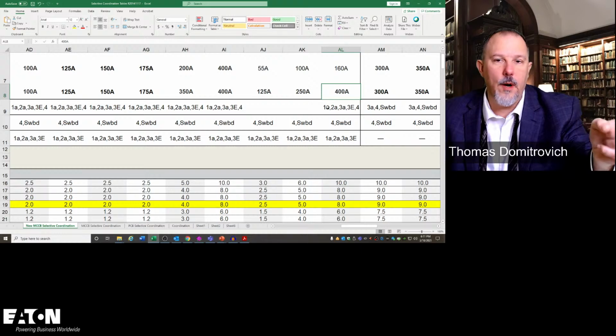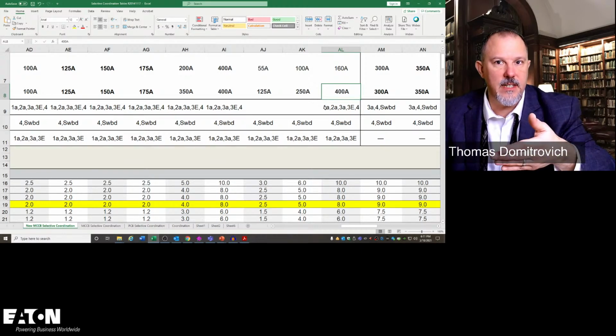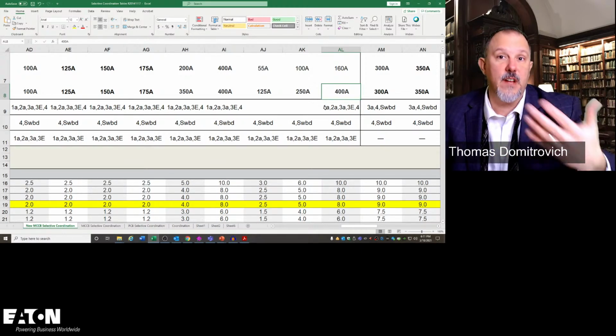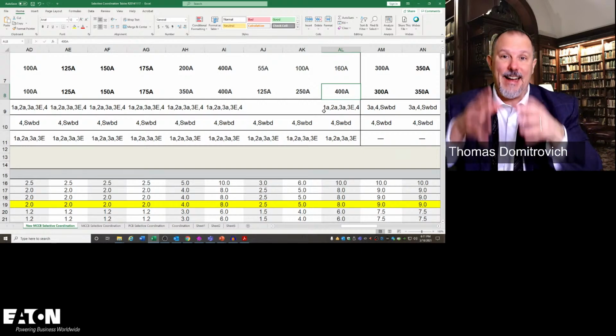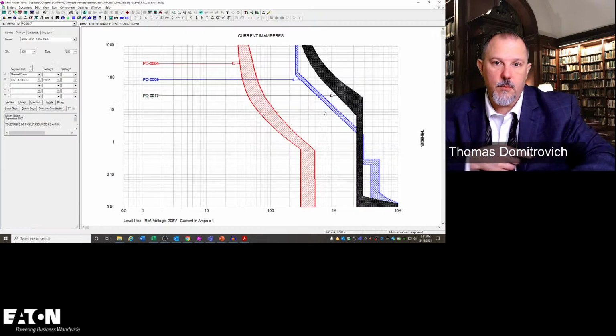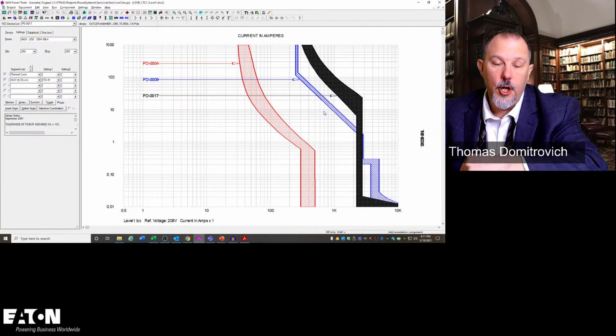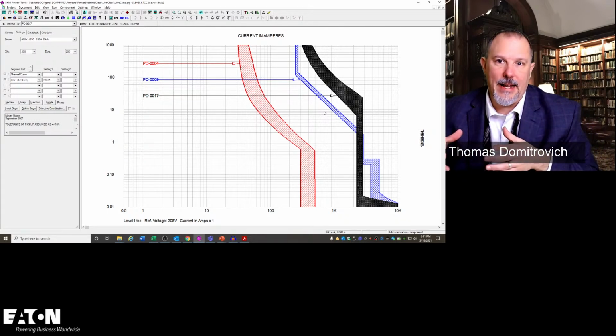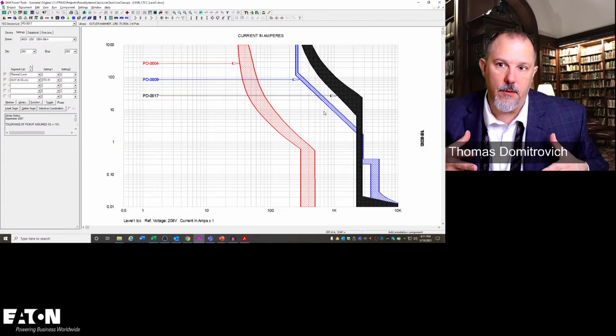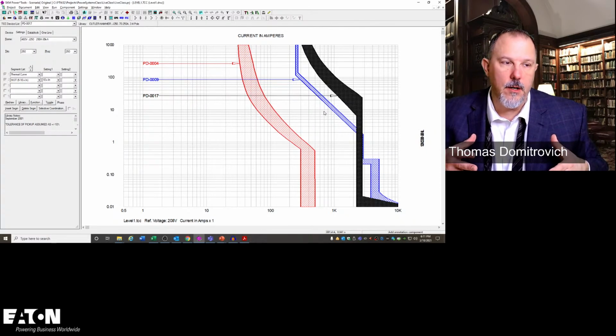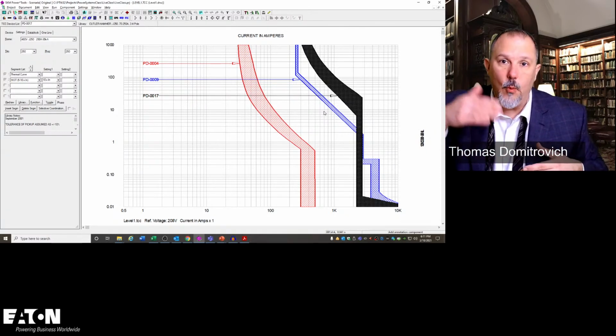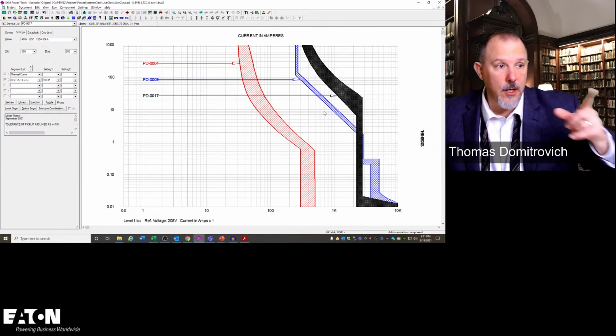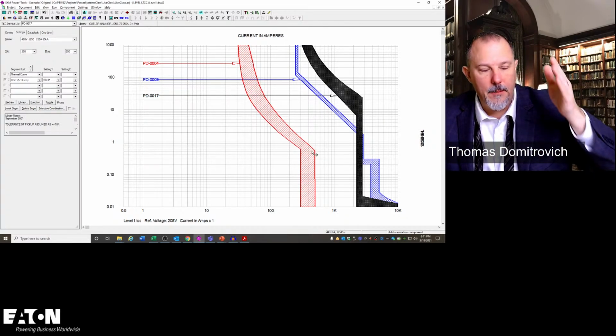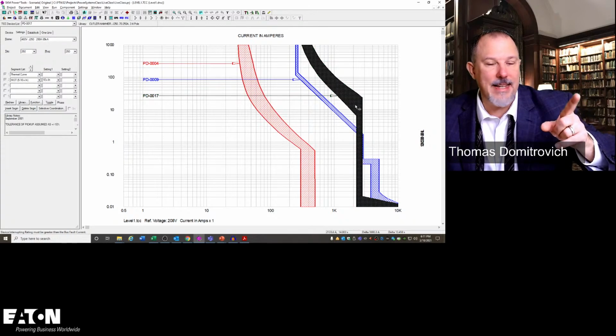You know what this means? 1A, lower dollars; 2A, a little bit more money; 3A, a little bit more money; 3E, a little bit more money; 4, you're looking at a little bit more money. So as you go up in these numbers, the dollar signs go up, and the more flexibility you have. This is the other aspect of selective coordination. When you're picking these circuit breakers, make sure you're looking at what equipment you plan to buy, what steel, I call it wrapping steel around the breaker. What will it fit, and where in the panel board will it fit? So I picked up a BAB 30. I can do this one. I can't do this one.